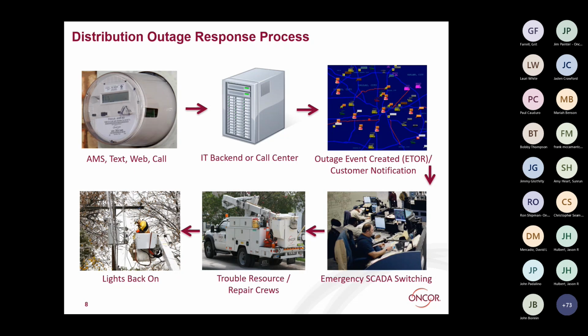Once it's isolated, then in parallel, resources are dispatched to patrol that line, just like what Ryan was saying, to literally identify the cause of the outage. There's really a multi-phase approach to that. The first phase is emergency switching: limit the exposure of the outage, isolate the fault, and restore power as much as we can. In parallel, resources are out there patrolling the line, hopefully finding that fault.